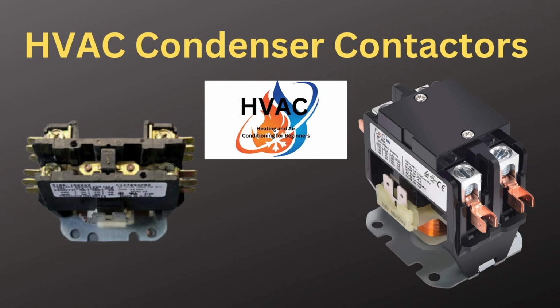The contactor on the HVAC system is usually on a certain side of the condensing unit that's outdoors. If you've never seen one before, it'd be the only thing on either side of your house or in the backyard that has some copper tubing connected to it. You might see a disconnect box and a concrete pad underneath it. That is your outside condensing unit. Then there's a little platform that has a door, usually with 4 screws or 2 screws, usually 5/16. You just unscrew the bottom ones, loosen the top ones, and pull the panel off, and you'll get access to the electrical panel on that condensing unit.